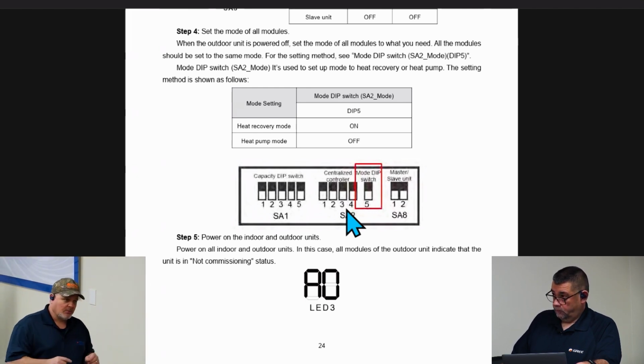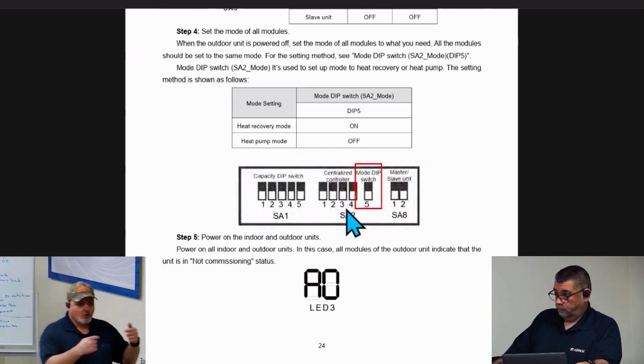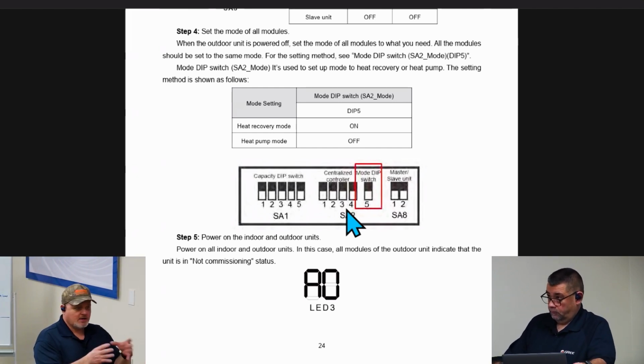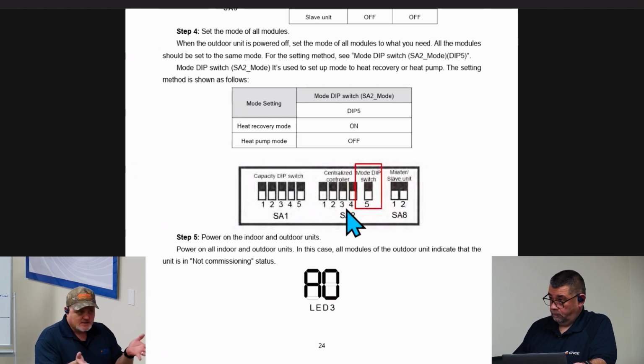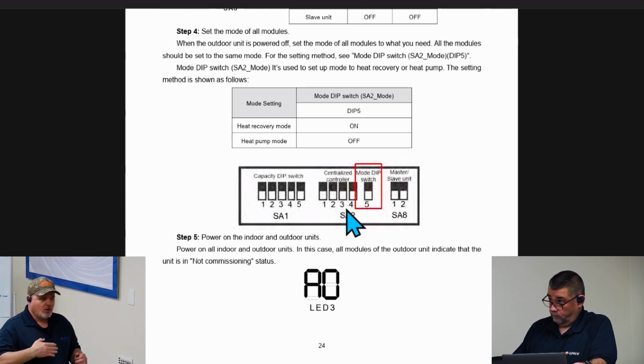Then on your third unit, it could be 1 unit or it could be a master-slave. Again, you're only setting the master, or if you only have 1 unit, it is the master of that unit, right? That one would be changed to unit number 3, and 4 and so on. And then you do that G1 and G2 wiring between those units only on the masters. You don't do G1, G2 wiring on the slaves. Only on the masters, you tie that wiring together.